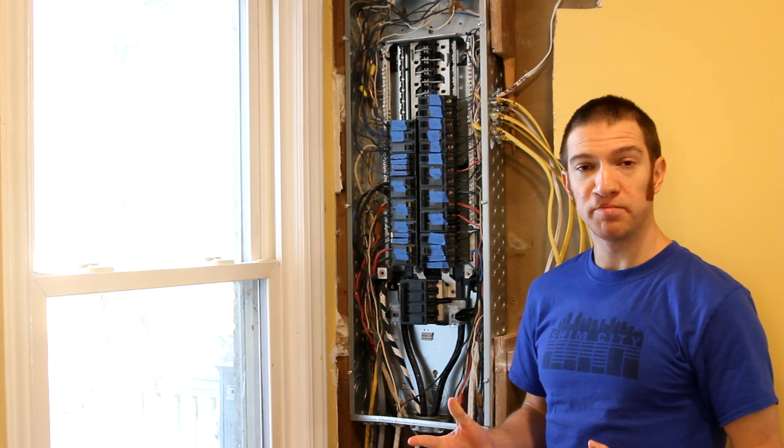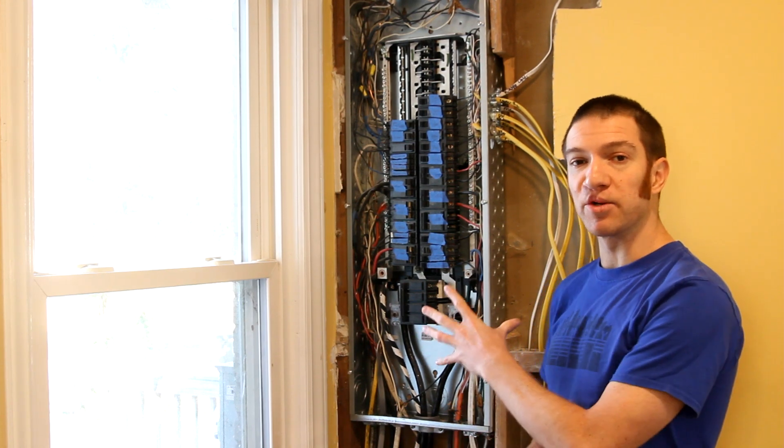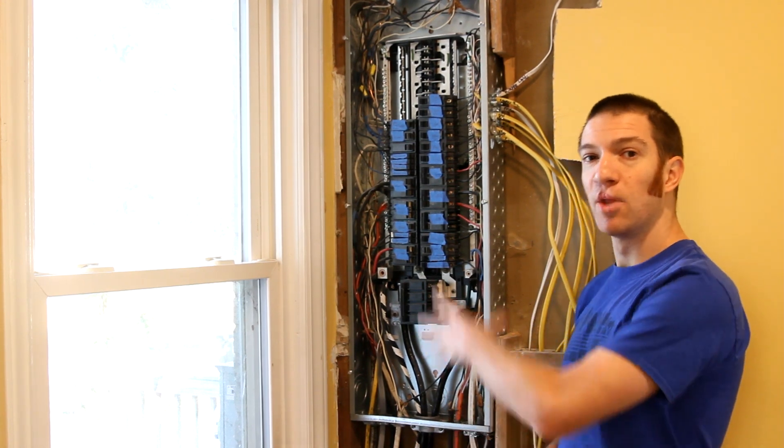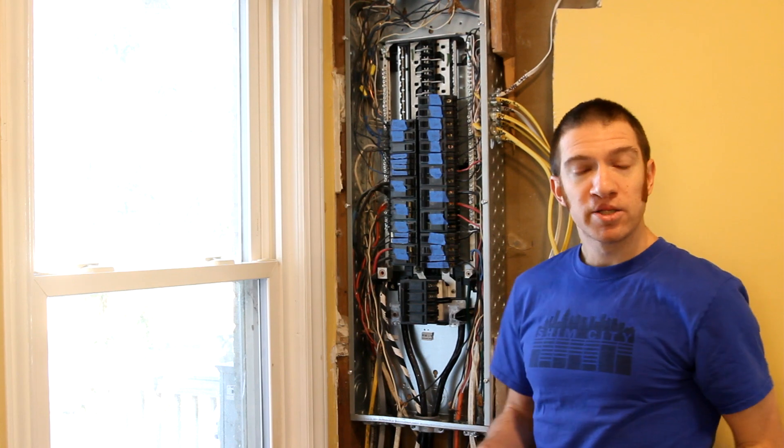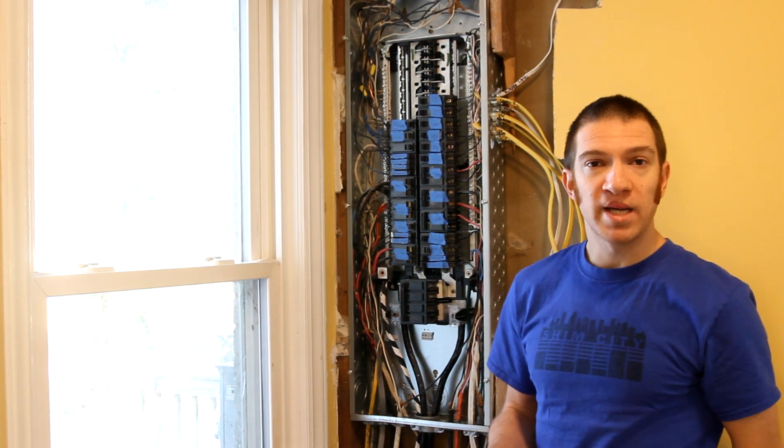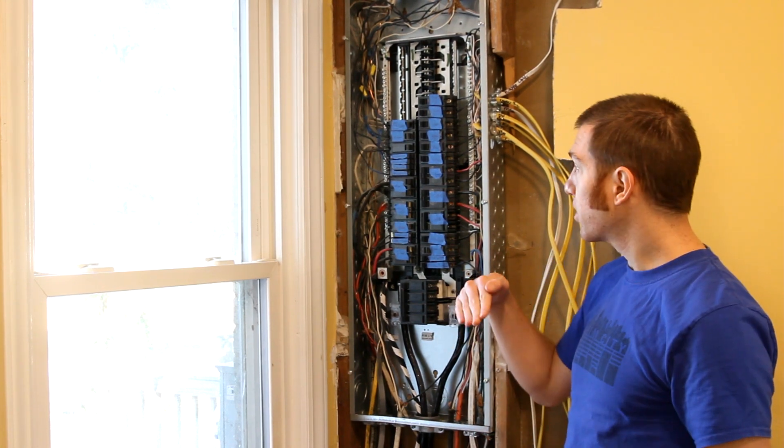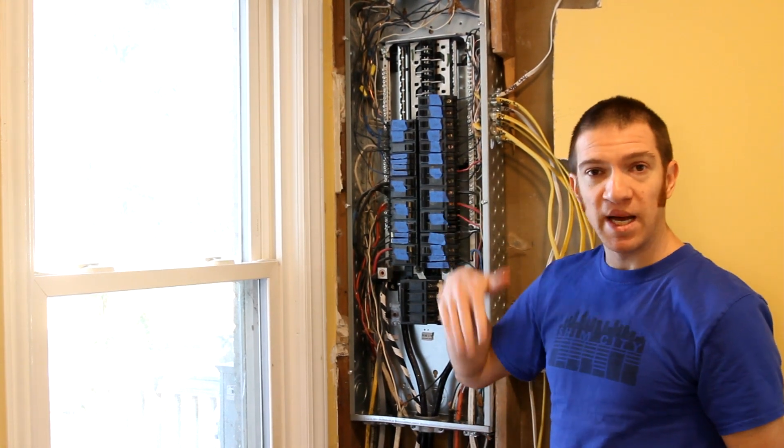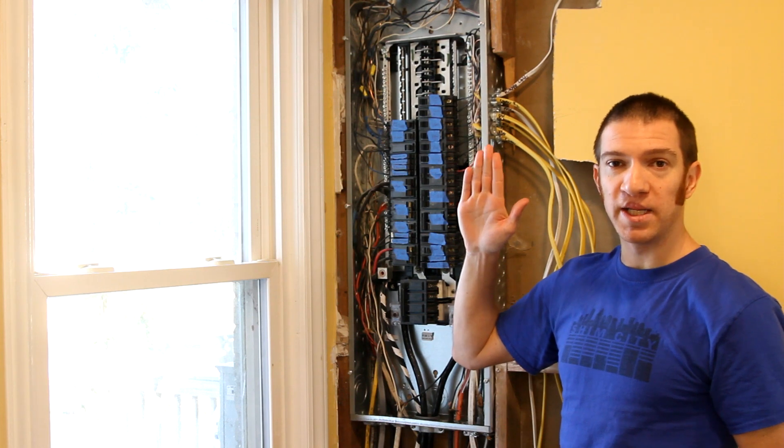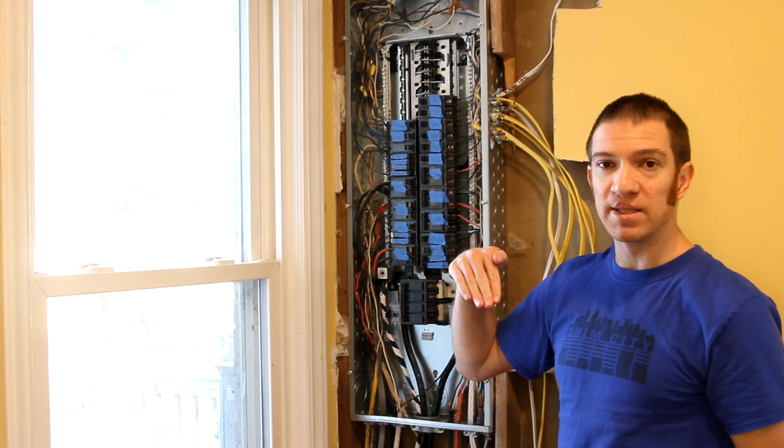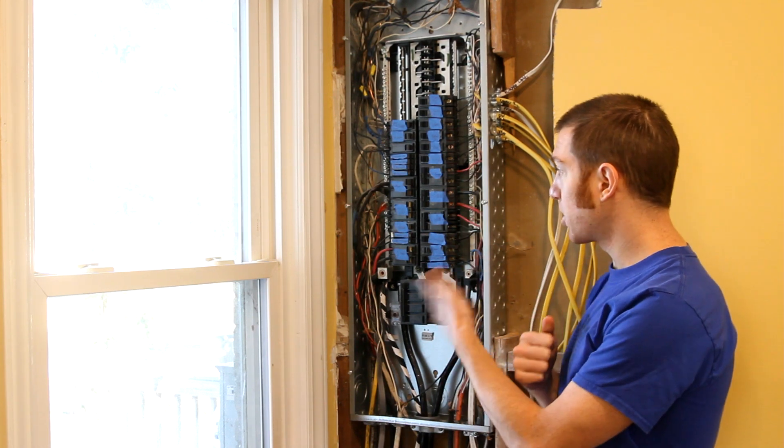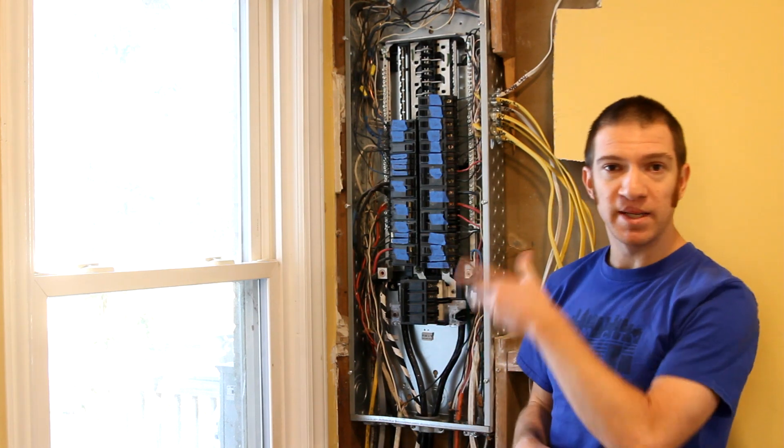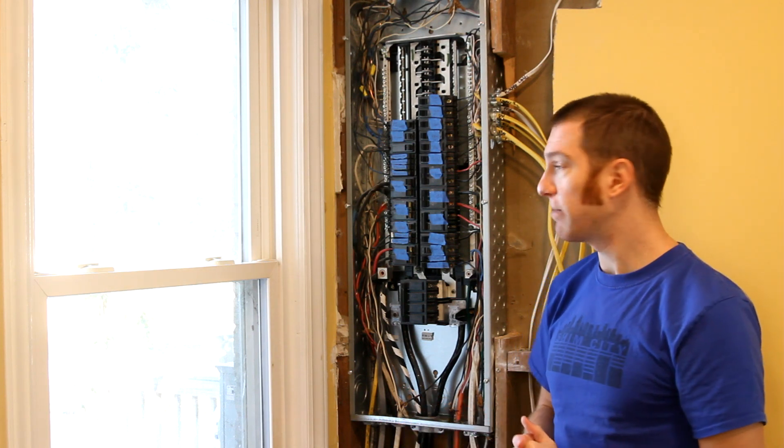Most modern panels can be installed with the main breaker either at the bottom or at the top. The main code requirement to look out for is if there are any breakers that flip up and down, then up always means on and down always means off. Since these breakers are all sideways, that makes it reversible, so you can flip the breaker at the top or the bottom.